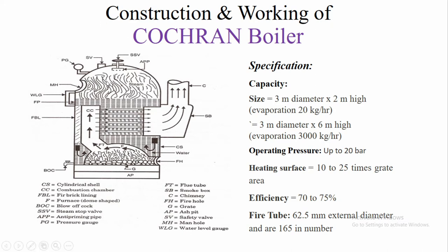Due to that heat transfer, steam is generated and stored at the top of the crown. The furnace is hemispherical so that if any unburnt fuel is carried with the flue gases, it strikes the top surface and returns back, resulting in complete combustion of the fuel and reduction in fuel loss.